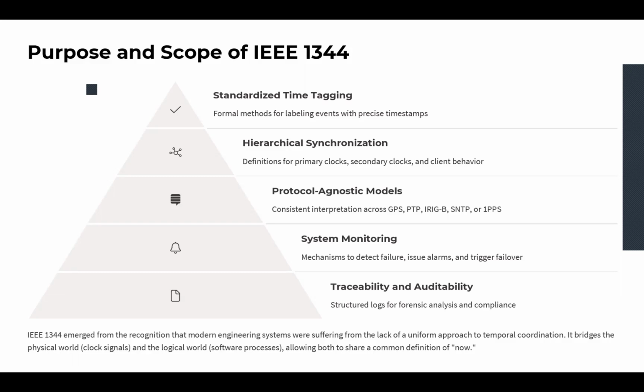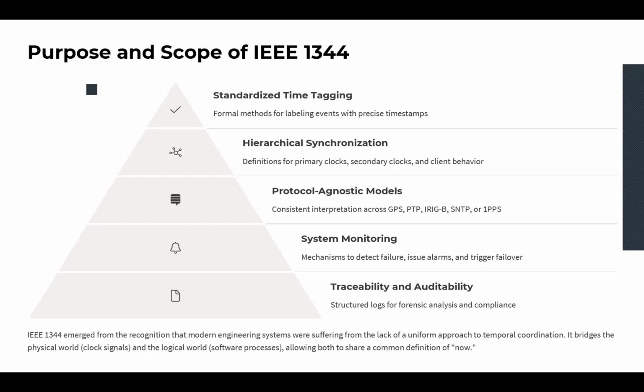What IEEE 1344 defines for this role is, first of all, we have to have a primary reference clock. So this is the hierarchy. We have a primary reference clock. It could be a GPS or an atomic source. We have grandmaster clocks, which basically distribute the time to the local subnetworks. We have boundary clocks, which are intermediate devices that pass time between domains. And we have an ordinary client, which is basically the end device that uses that time tag, like relays or PLCs or PMUs that we discussed.